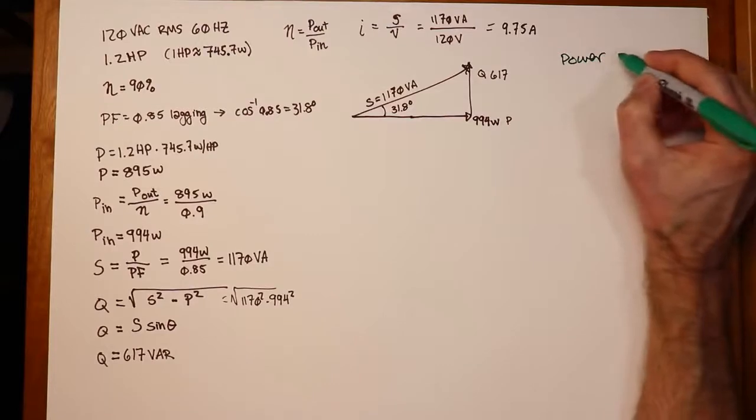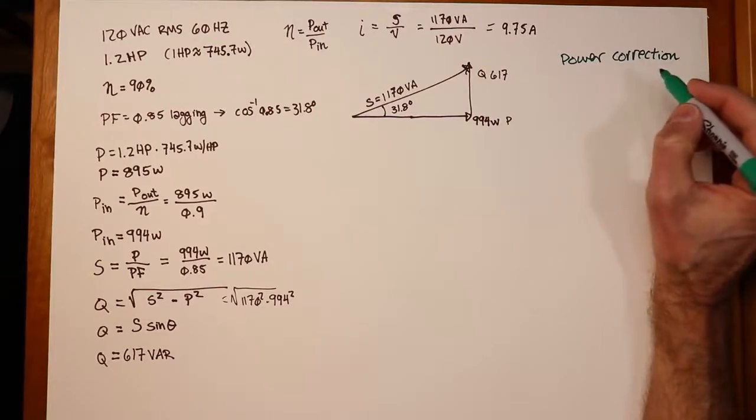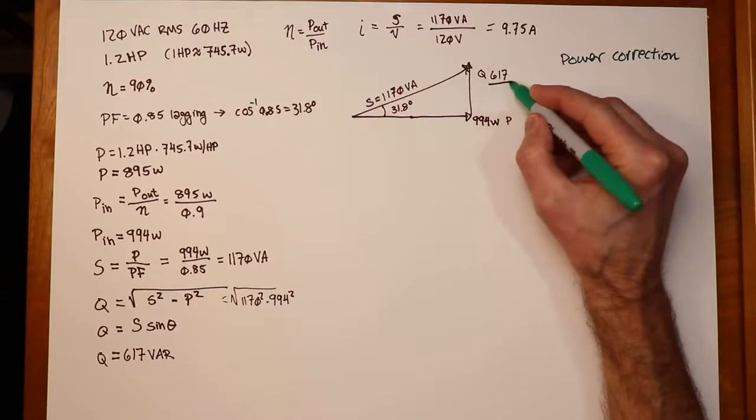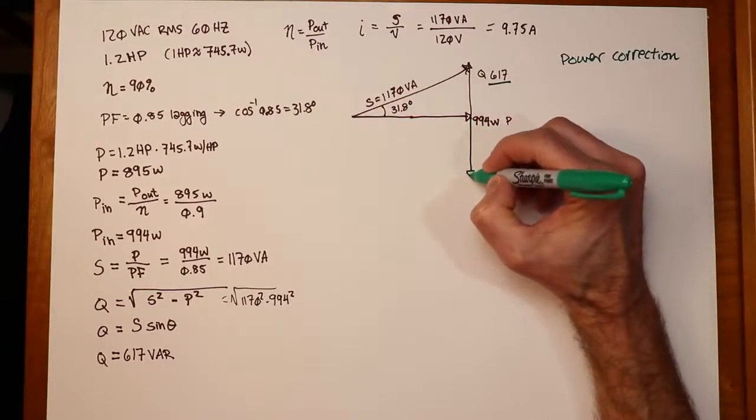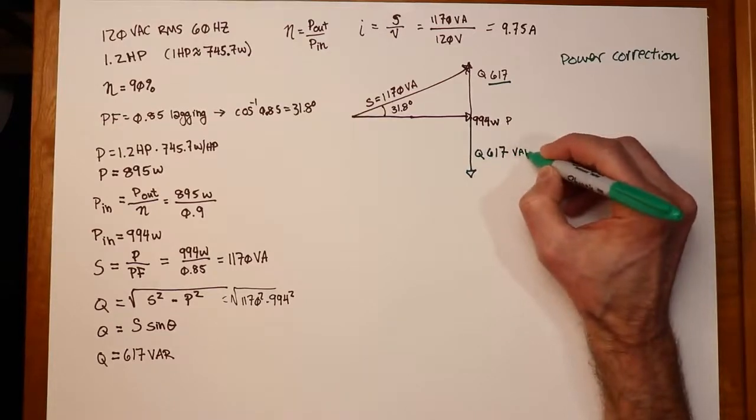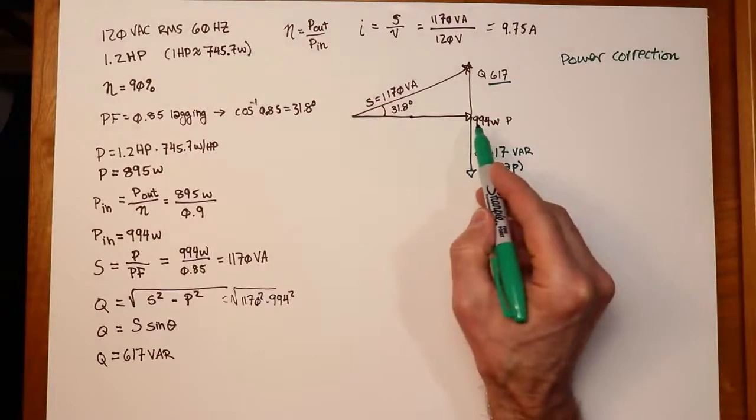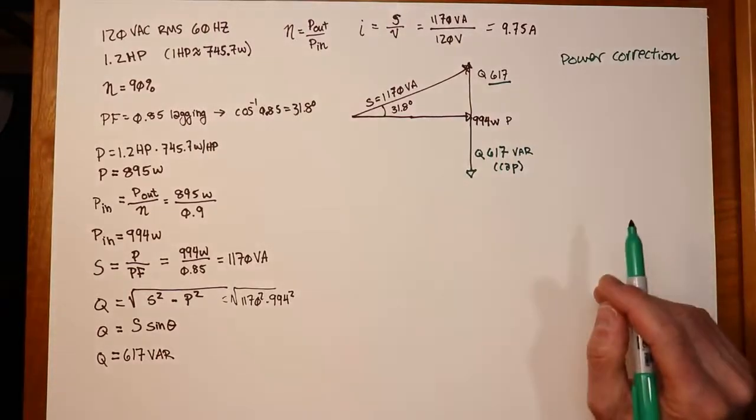Now, that sort of completes this situation. At the close of the prior video, we had mentioned that we could do power factor correction. Power factor correction. The idea here was to reduce the current draw. So the power factor correction, the idea here, would be to introduce a Q value that's the same magnitude, but in the opposite direction. In other words, I want to introduce a Q that's capacitive, but also equal to 617 var. Just capacitive this time. So this and this will cancel out. S will collapse down onto the P vector. In other words, S will be 994 volt amps or watts. It would be the same thing at that point.